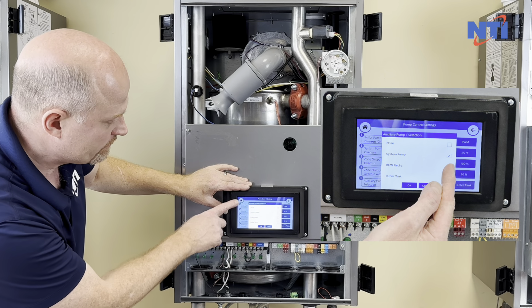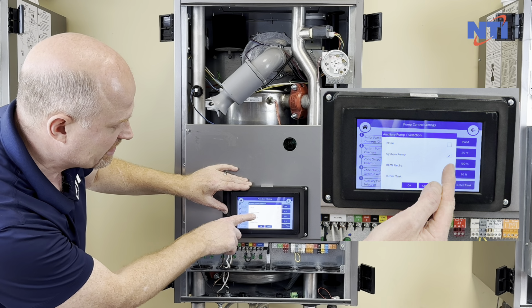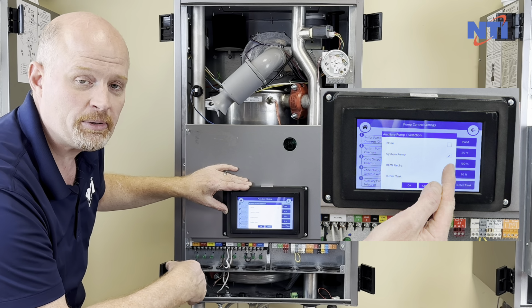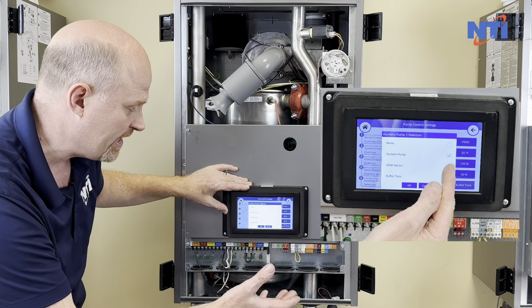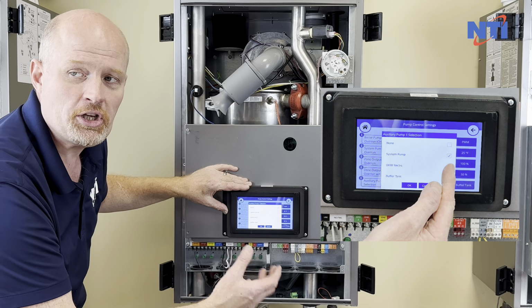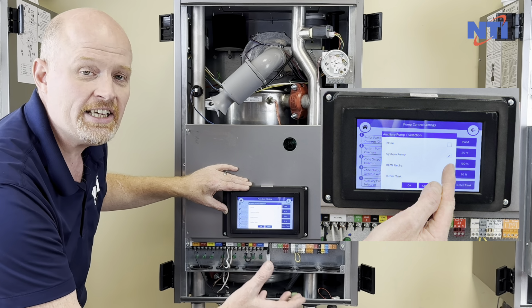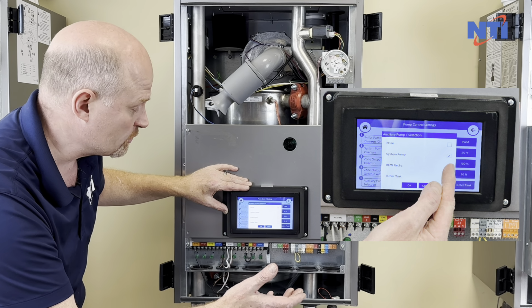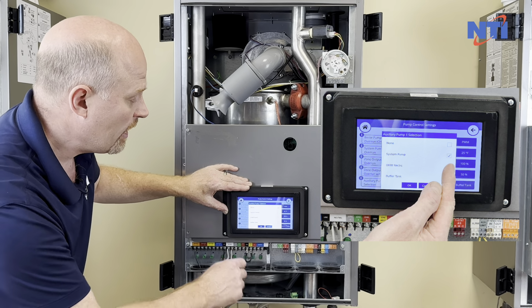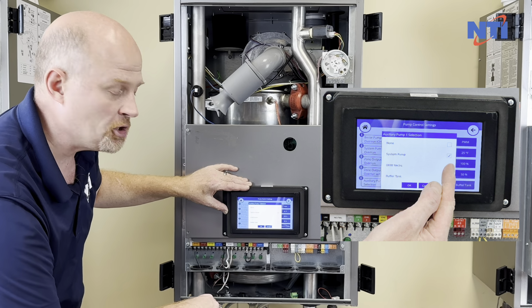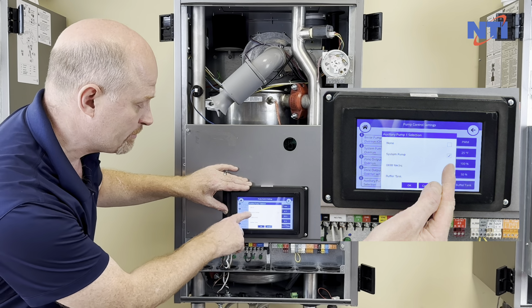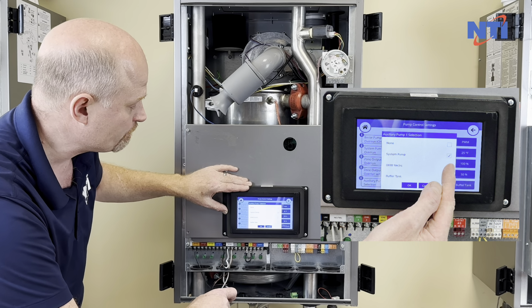Touch the blue box, and Auxiliary Pump 1 can be set as a system pump. Now, a system pump is a pump that would typically go downstream of the boiler in the heating system, and it's a pump that you want to run for any heating call. Now, you may choose to run this for a domestic call as well, and you can choose not to. So if you select system pump and you want it to turn off for domestic, you need to go into the menu to change the system pump operation. I'll show you that in a moment.